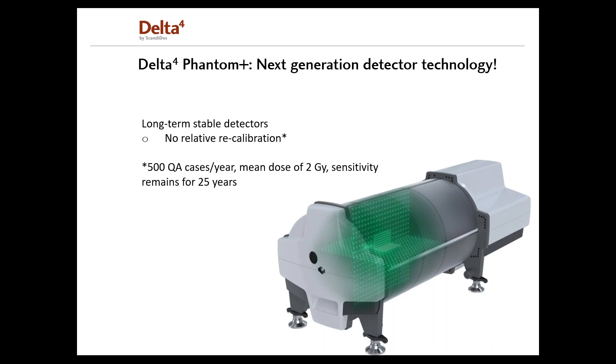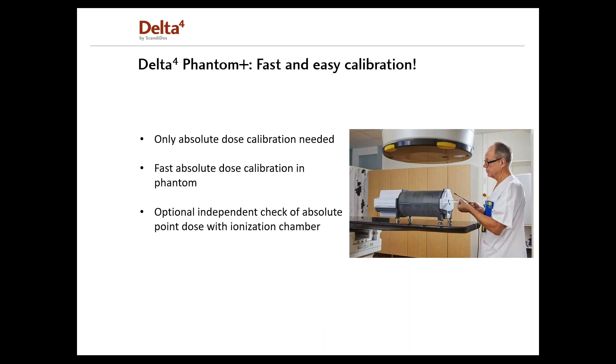Therefore, there is no need to perform relative recalibration or directional recalibration at the clinic. The cylindrical Phantom also has inserts for different ionization chambers, allowing absolute dose to be verified with an ionization chamber directly in the Phantom. This also allows absolute calibration to be performed without any disassembly of the Phantom, which is convenient when calibrating on different accelerators or when required by regulatory requirements. Inserts are available for common cylindrical chambers like the Farmer, the Semiflex, and others.